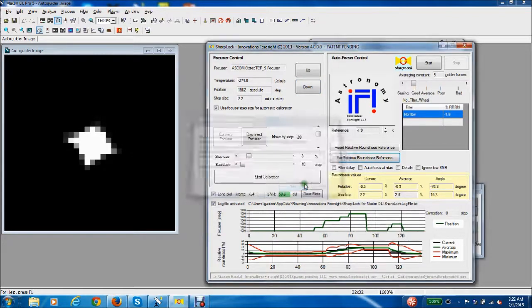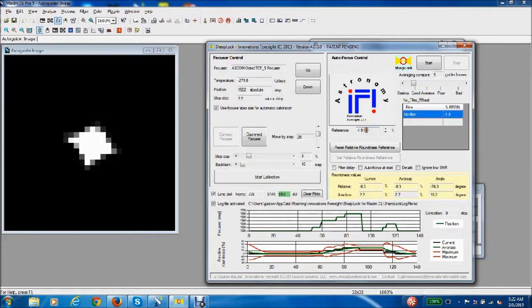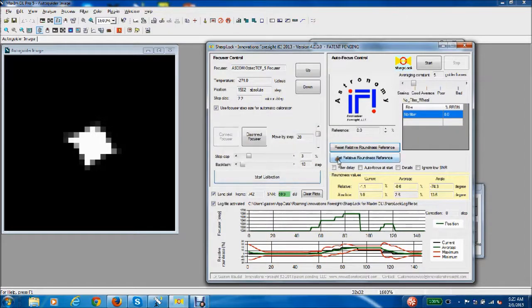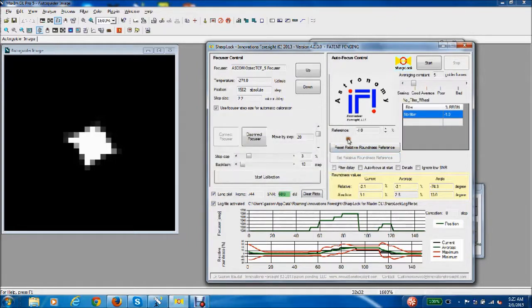As I said, it should be below 3%. And you can see the value here. If you want, you can change it up and down anytime. You could do that if you have any reason to do that, but I would suggest not to do this. If this value is below 3%, it's good enough. You can clear it if you have a problem and reset it to the current average of the relative roundness of the system. This is your baseline for the autofocus.